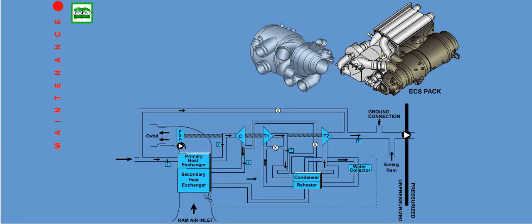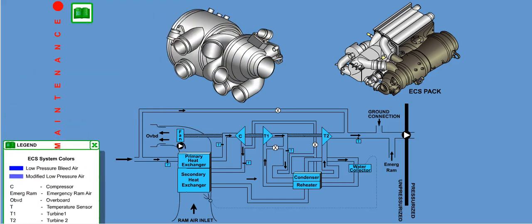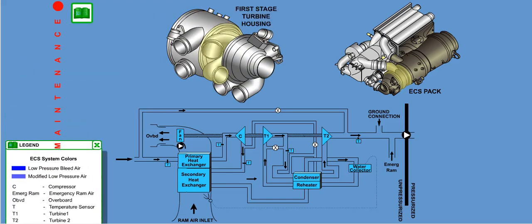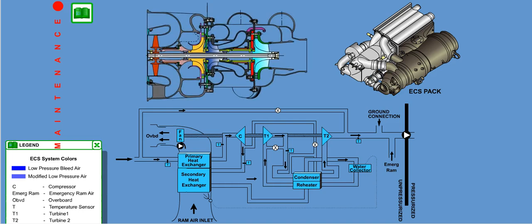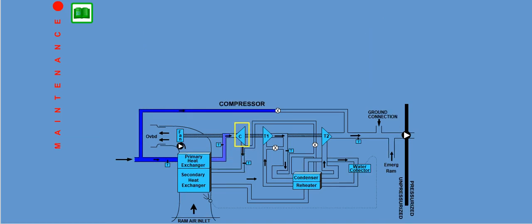The air cycle machine external structure has three components: fan and compressor housing, first stage turbine housing, and second stage turbine housing. The internal structure incorporates two turbine stages which drive a compressor and a cooling fan. The 4 rotors turn as one assembly, locked together in the common shaft. The assembly rotates on hydrodynamic foil-type bearings. The system uses no oil and requires no scheduled maintenance. The air cycle machine compressor will raise the air temperature and increase pressure in order to provide more effective cooling on the turbine stages.